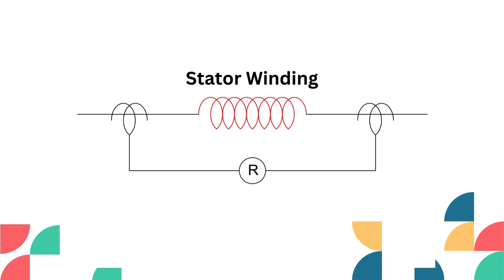The logic behind generator differential protection is very simple. It simply relies on the current balance principle. This means the incoming and outgoing current of a path should be the same. As long as this condition is fulfilled, the relay will not operate. But whenever there is a fault in the winding, the balance will be disturbed and the relay will operate.